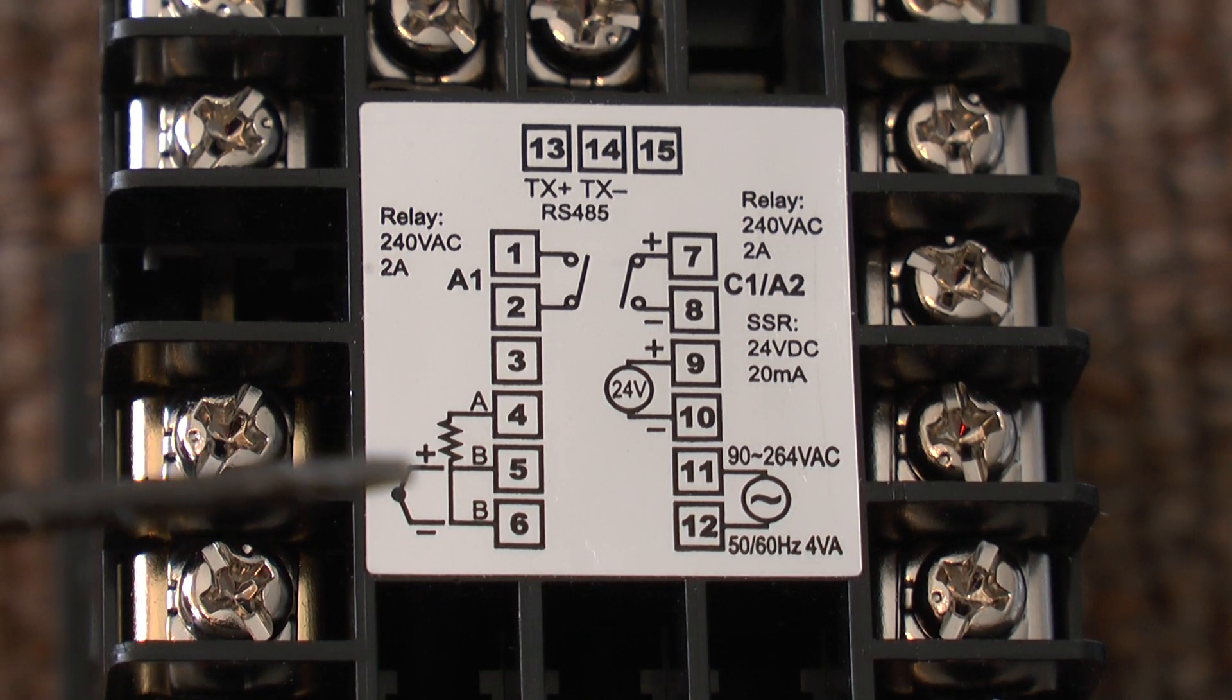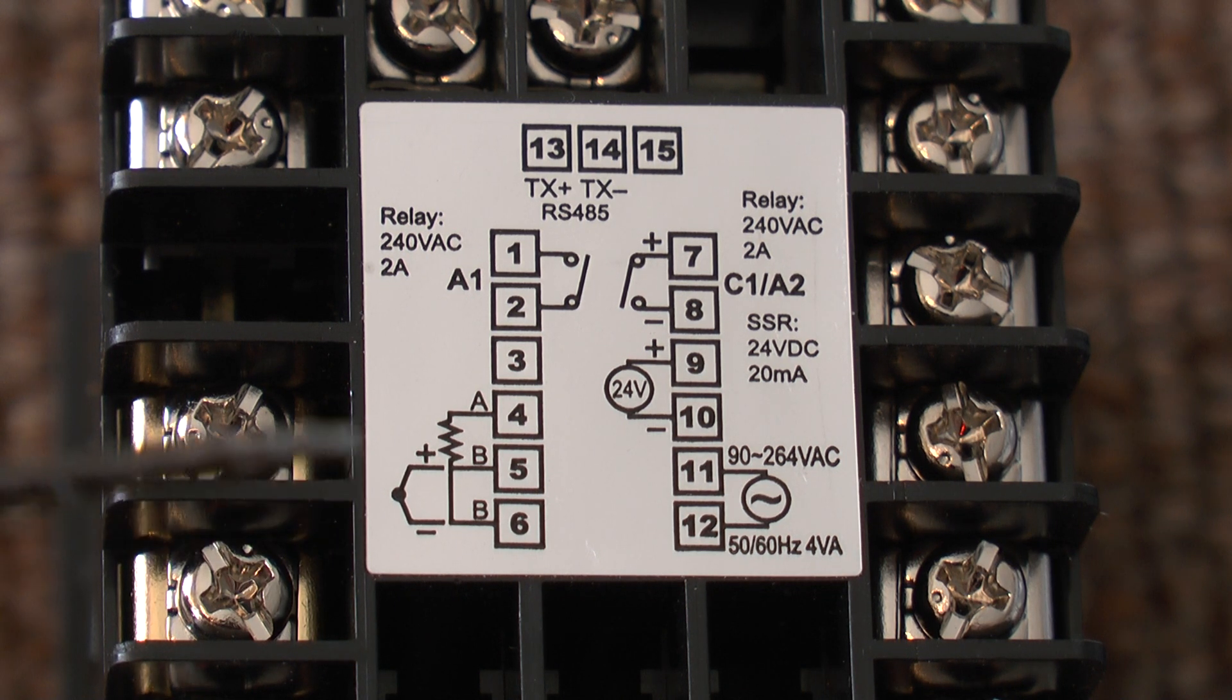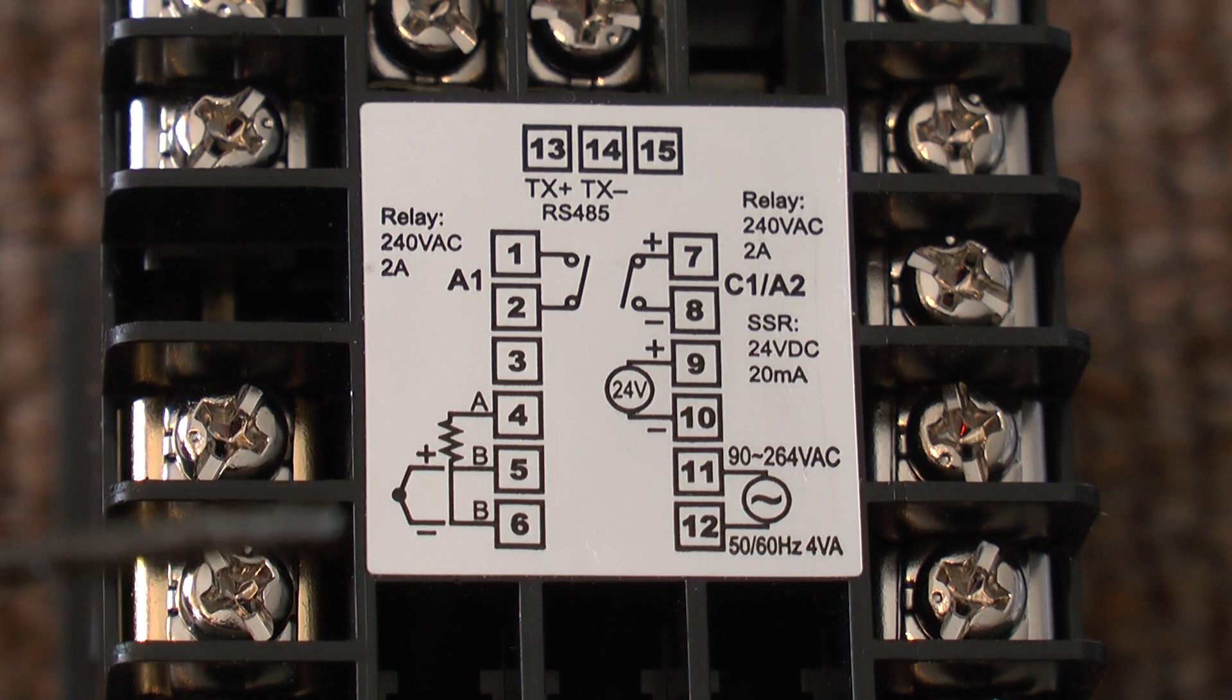Your thermocouple or sensor will be connected to terminal 5 and 6. Terminal 5 being the positive and terminal 6 the negative.